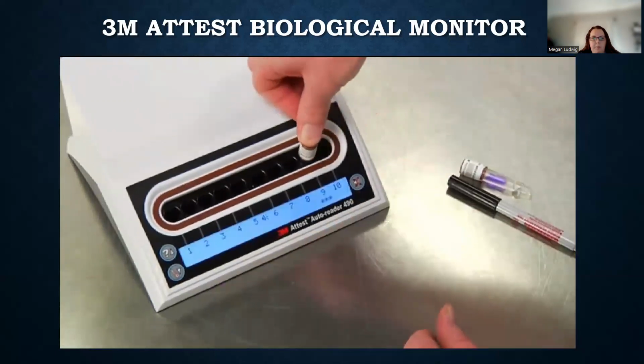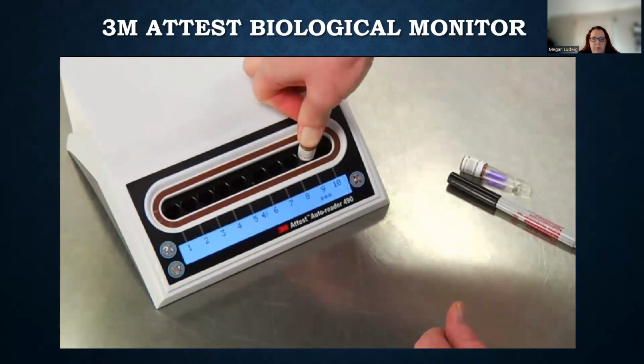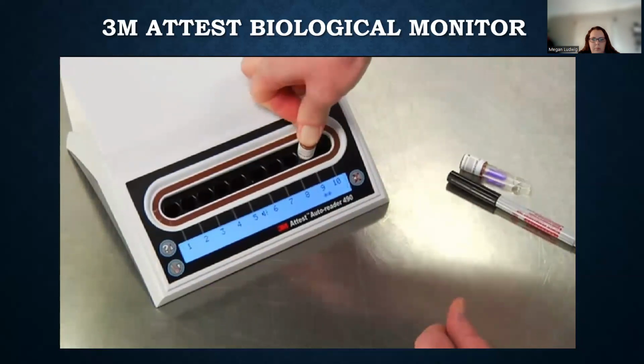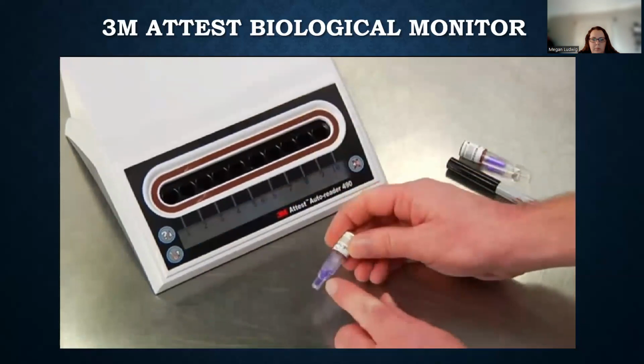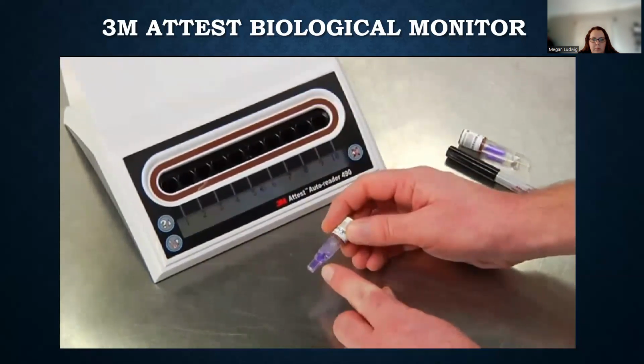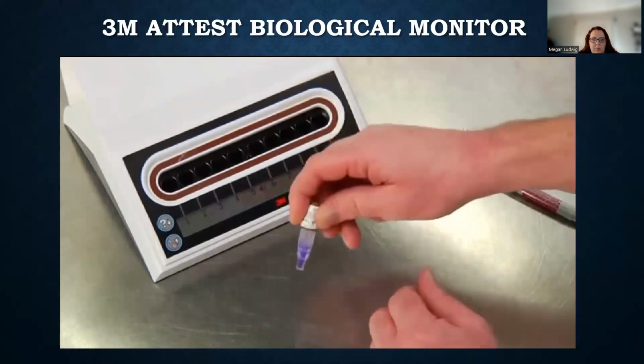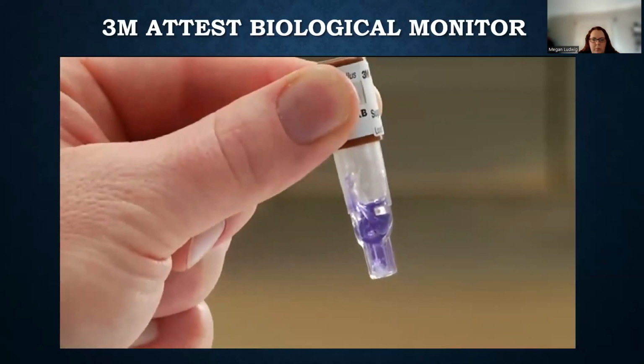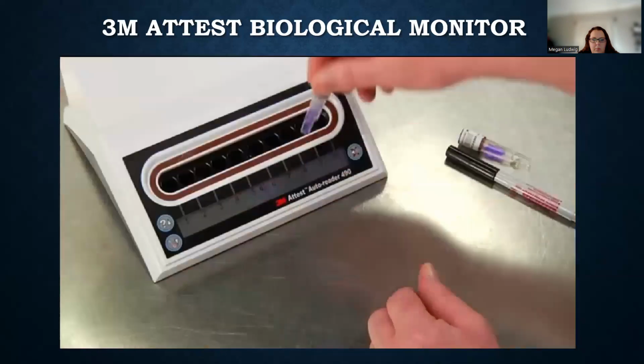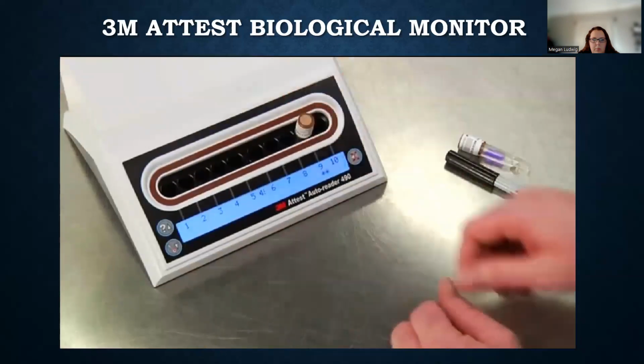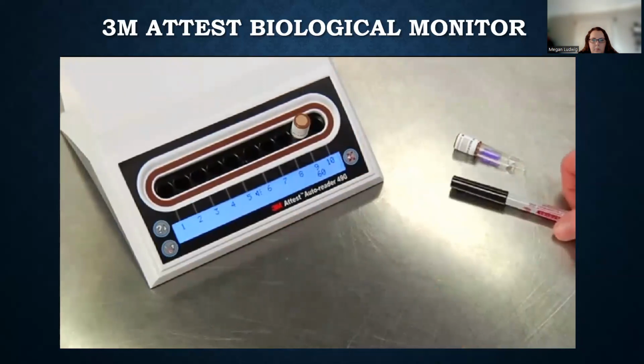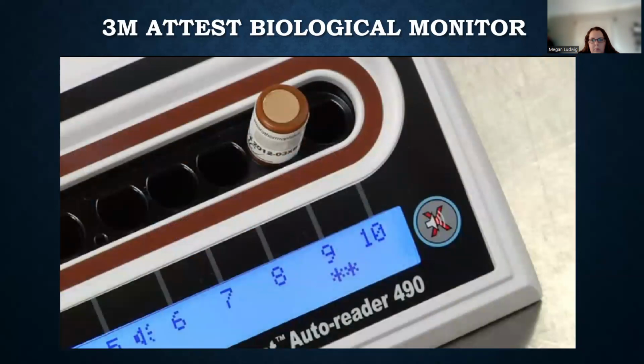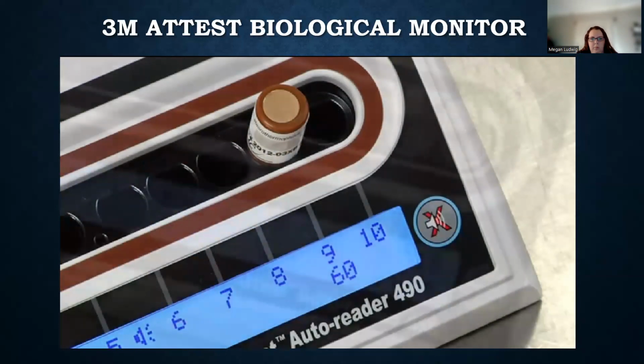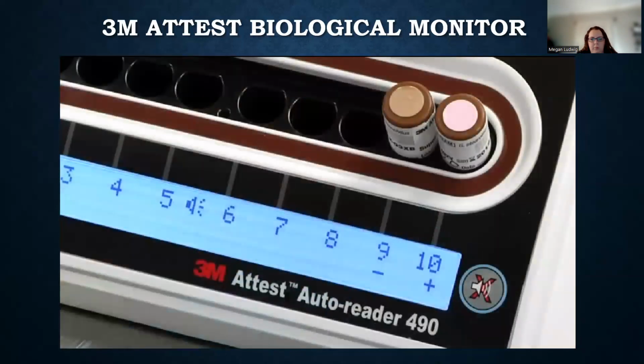Press the cap of the Attest Super Rapid BI down firmly to close the cap and crush the glass ampule. Immediately remove the BI and visually verify that the glass ampule has been crushed. Then, flick the vial to cause the purple growth media to flow to the growth chamber at the bottom of the vial. Return the activated BI to the incubation well and check the LCD panel to confirm that the vial is properly seated. The Auto Reader LCD panel will display a series of asterisks, then the remaining incubation minutes right below the incubating BI. Now, all you need to do is wait for the result.